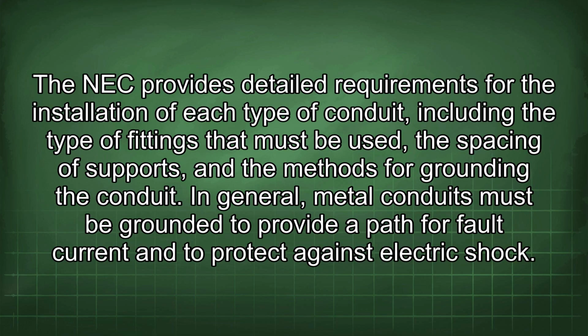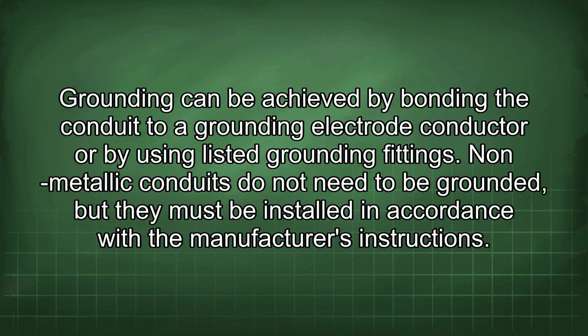The NEC provides detailed requirements for the installation of each type of conduit, including the type of fittings that must be used, the spacing of supports, and the methods for grounding the conduit. In general, metal conduits must be grounded to provide a path for fault current and to protect against electric shock. Grounding can be achieved by bonding the conduit to a grounding electrode conductor or by using listed grounding fittings. Non-metallic conduits do not need to be grounded, but they must be installed in accordance with the manufacturer's instructions.